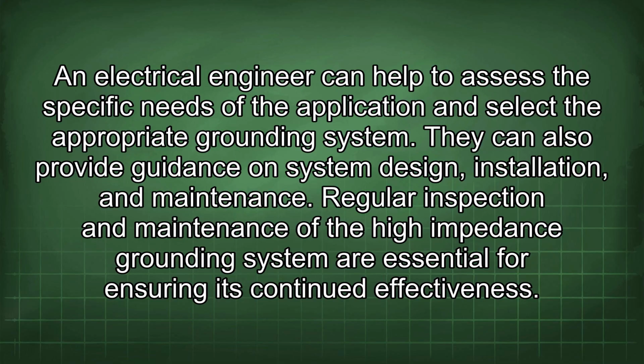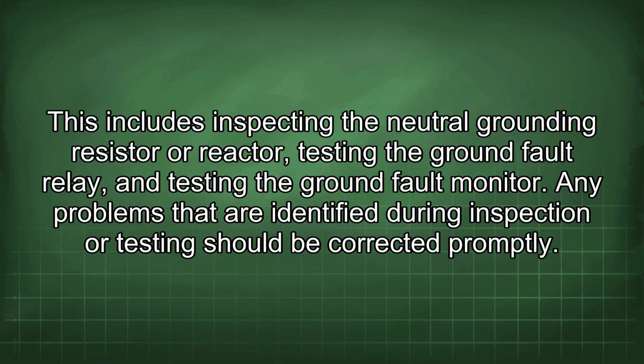Regular inspection and maintenance of the high-impedance grounding system are essential for ensuring its continued effectiveness. This includes inspecting the neutral grounding resistor or reactor, testing the ground fault relay, and testing the ground fault monitor. Any problems that are identified during inspection or testing should be corrected promptly.